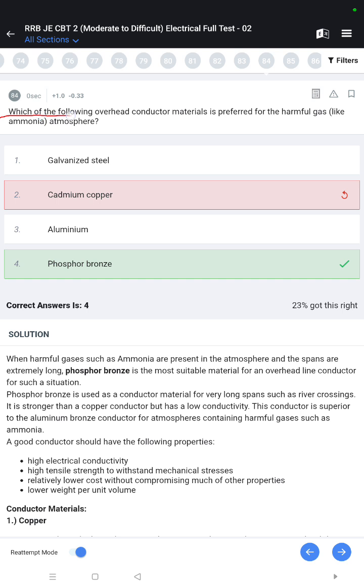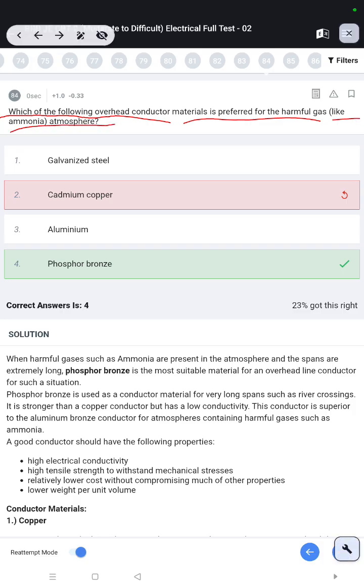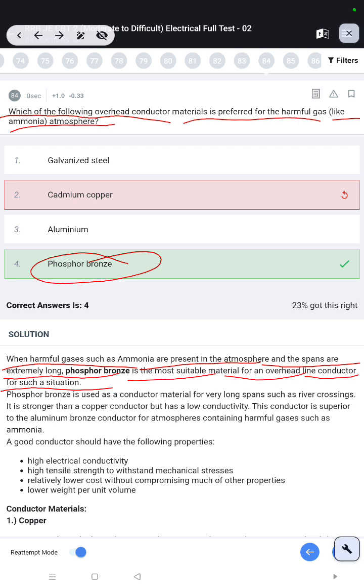Which of the following overhead conductor materials is preferred for a harmful gas like ammonia atmosphere? Phosphor bronze. When harmful gases such as ammonia are present in the atmosphere and the spans are extremely long, phosphor bronze is the most suitable material for an overhead line conductor. For such a situation, phosphor bronze is used as a conductor material for very long spans, such as a river crossing. It is stronger than a copper conductor but has low conductivity. This conductor is superior to aluminum bronze conductor for an atmosphere containing harmful gas such as ammonia.